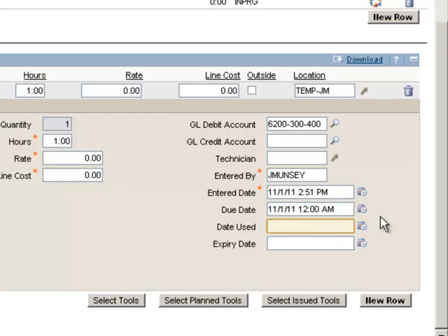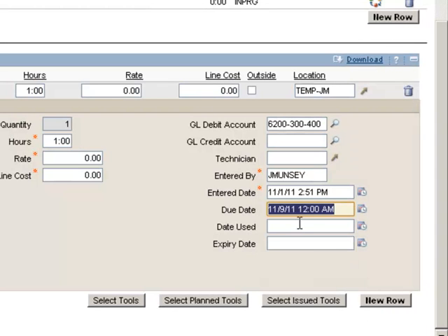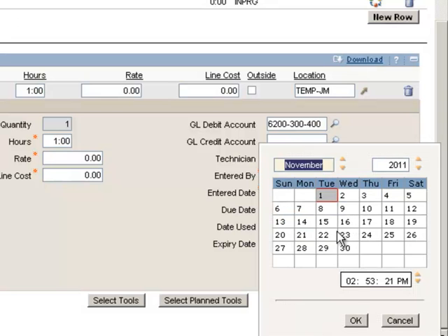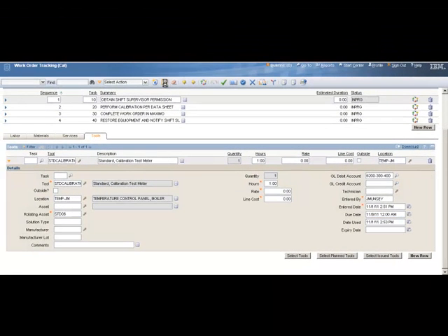Now, depending on how you configure your setup here, I can actually change this date. It could be that this is not correct, and I know it's not due till the 9th and just hasn't been updated yet in the system. So I'm going to make sure that my current one, based on a calibration due date on a sticker, is correct. And here's my date used, my date due for my instrument. And I want to record this. This is my indication that this calibration was performed with a valid standard. So I'm going to set that up, hit the save button, make sure everything's okay. And if it saves, you're good to go. And I've associated my calibration standard to my calibrated instrument now.